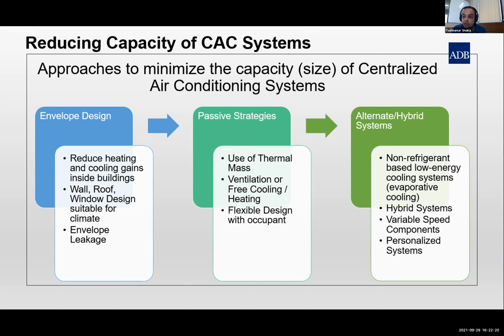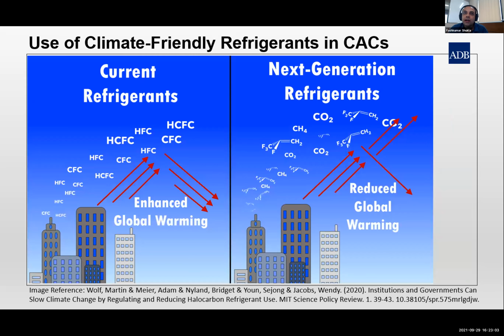You can think about variable speed components and very personalized systems, asking how we can have systems which provide comfort specifically to the occupants. It is also becoming quite useful to think about hybrid systems, where two or three technologies are integrated into the air conditioning system, and you use the technology most suitable for that period of the day or period of the year. So a hybrid cooling system is another way we can reduce capacity, because now you don't have to size your system for the entire cooling need of the building, but you can cut it down into small pieces and use certain components.